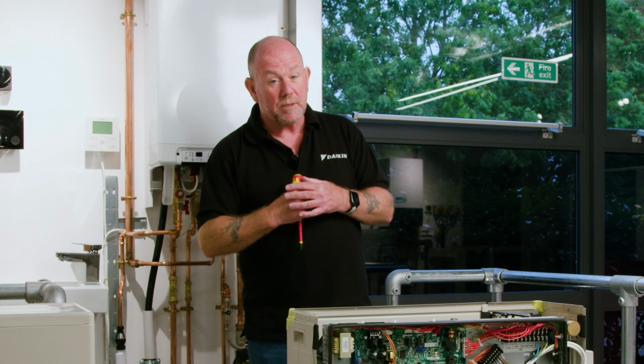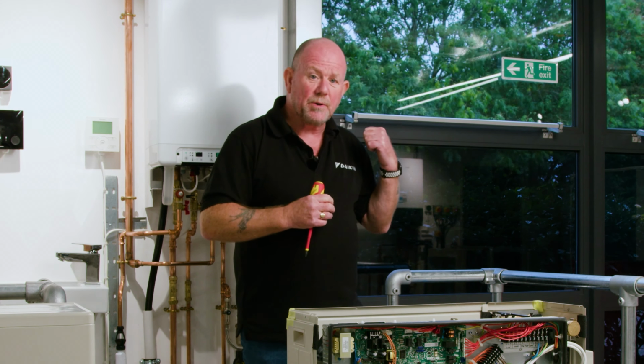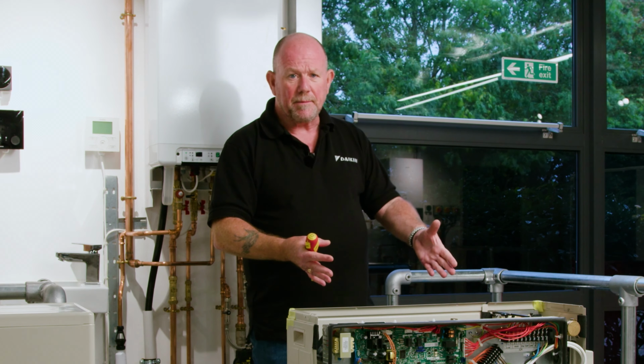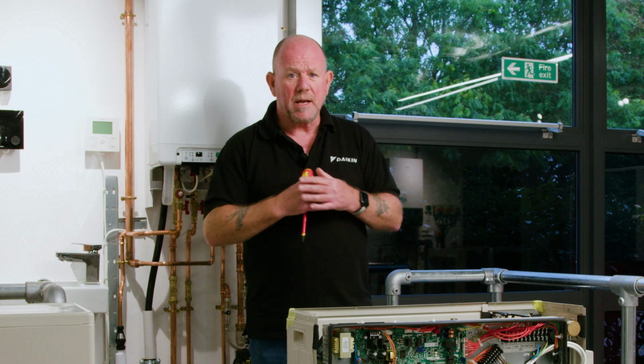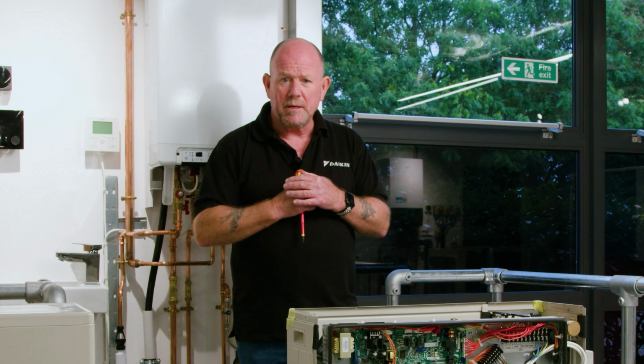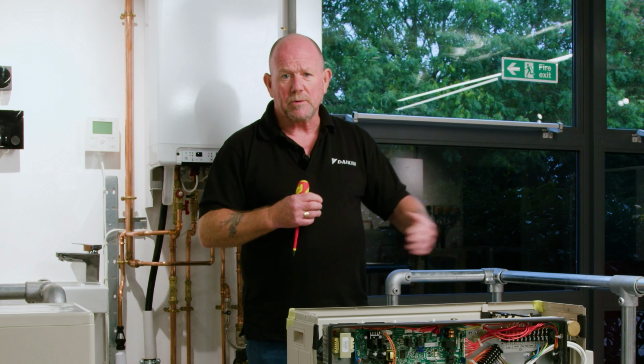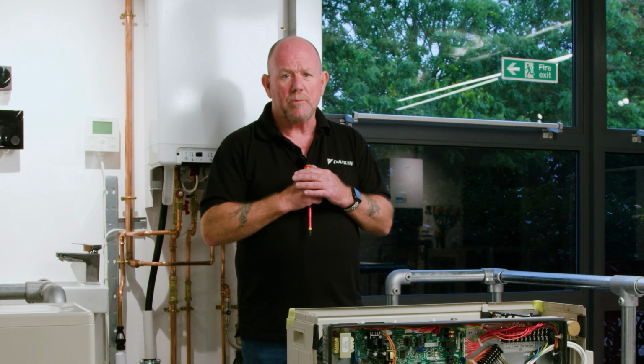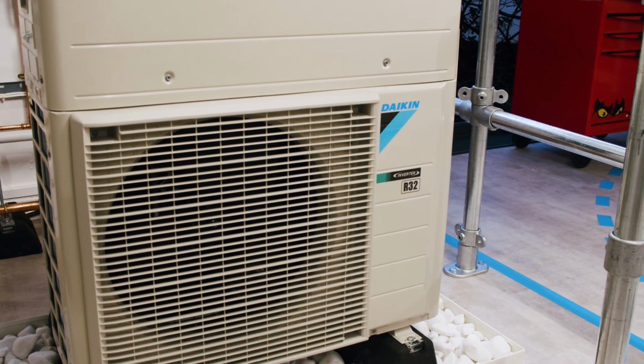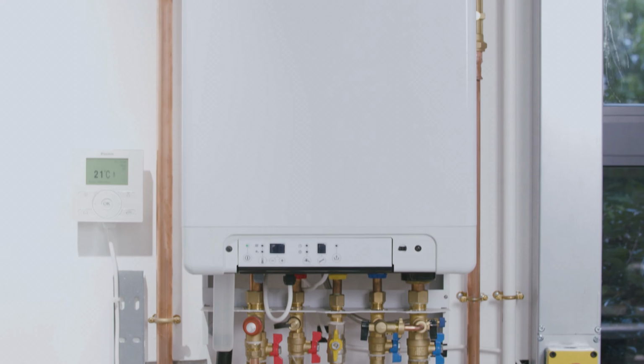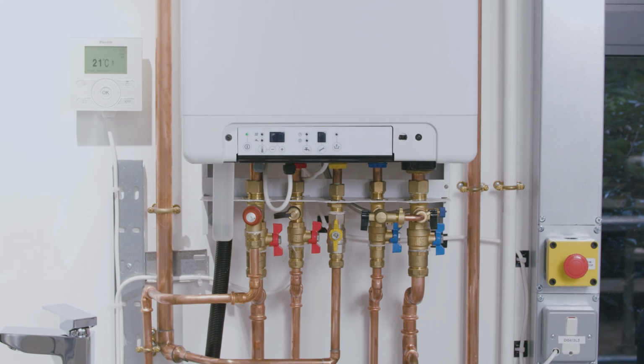There are, of course, 2 power supplies required, one for our gas boiler and one for our outdoor unit. The gas boiler needs a standard 3 amp supply, so will come off the house ring main. It's a separate supply for the outdoor unit, and a 20 amp supply will be required. The refrigerant circuit is all done at the factory, so the connections on site are all water connections. Simply pipework between the outdoor unit and the boiler, and then back to the outdoor unit.